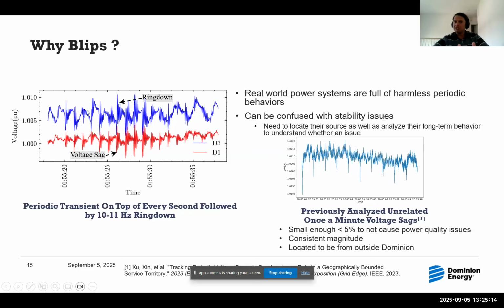If you look at this ring down data through a mode estimation lens, it yields a mode in the 10 to 11 hertz range. That means there must be some kind of periodic forcing in this part of the system that is exciting this particular 10 to 11 hertz mode.